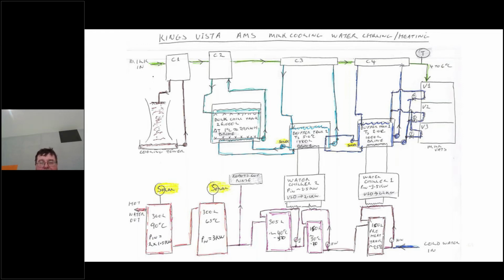As you see, I've got solar marked in various points. Solar's providing all our hot water at the moment. We don't use any night tariff for hot water anymore. You see 2 solar marked at the buffer tanks. When we've got excess solar, it's obviously chilling the bulk tank. Now, the bulk tank is 26,000 litres, and just as an interest, every degree change in that tank is equivalent to 29 kilowatt hours. So you can see it's a large battery in itself. And when it's down, the temperature should do a real good job.